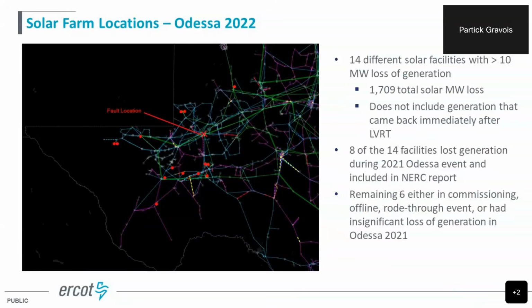I want to be clear, we're not including generation that reduced megawatts and came back immediately after low voltage ride through, because that's allowed. We expect these units to drop some megawatts proportional to voltage. The voltage is dropping, so of course the megawatt output is going to drop as well, and they're also trying to provide reactive current during this fault condition.